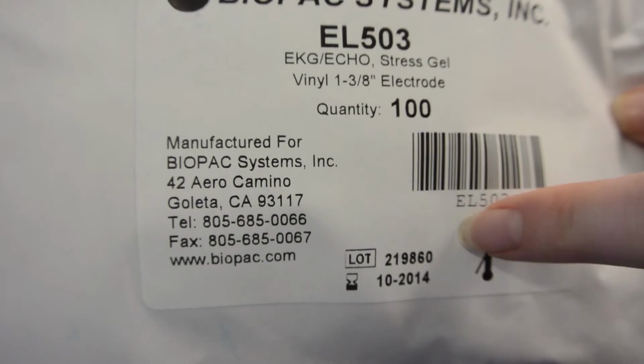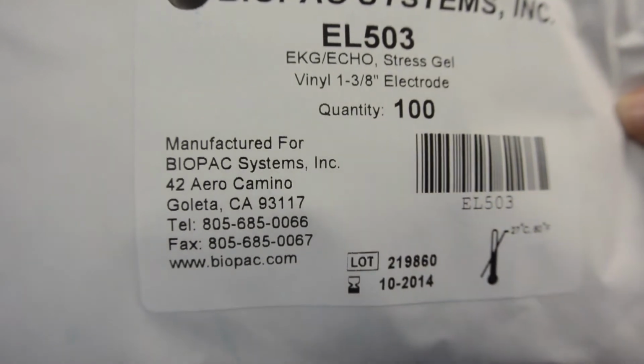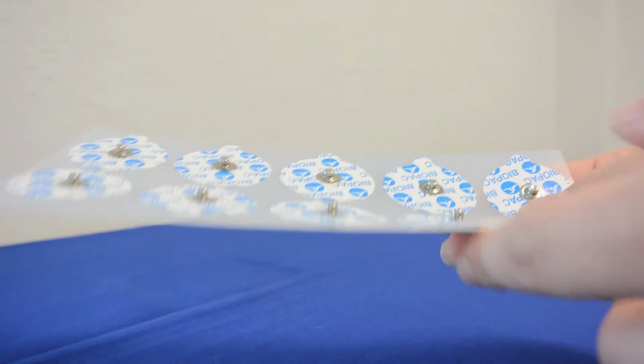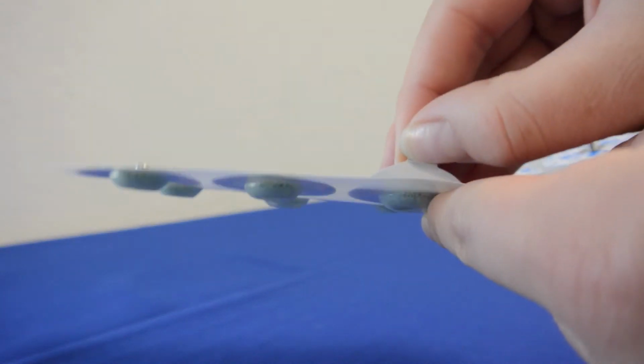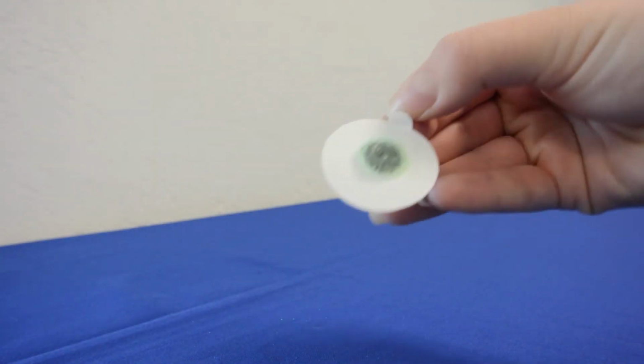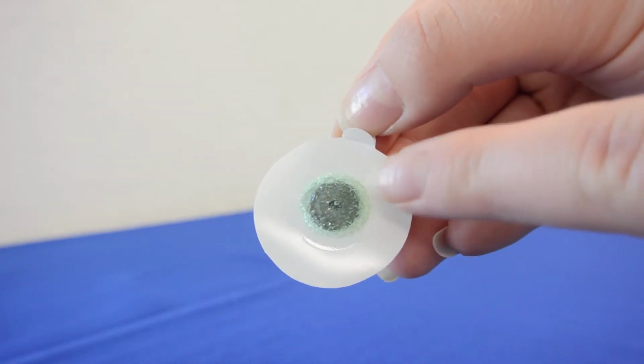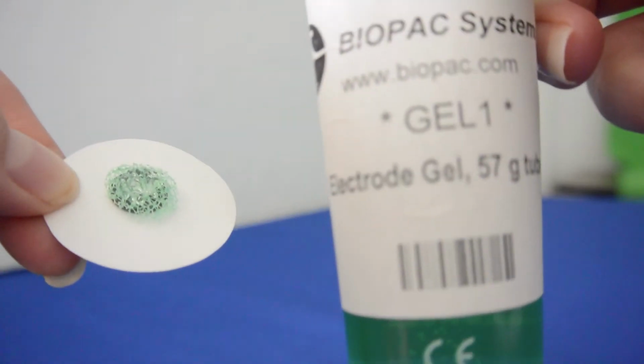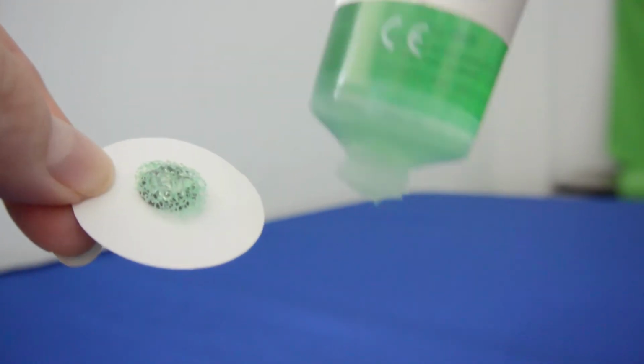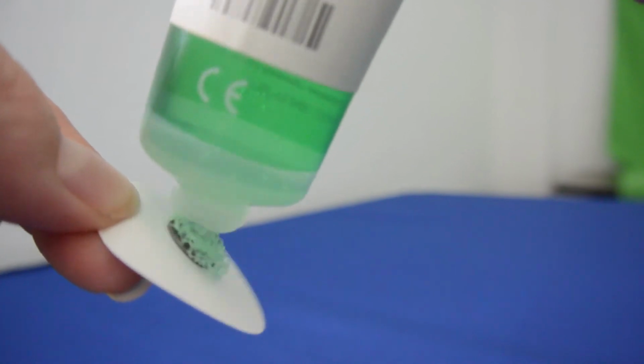Next, verify the expiration date of your electrodes. Now, remove an electrode from its backing and verify the gel content on the electrode. If the electrode is slightly dry, you can regel the electrode using any standard electrode gel.